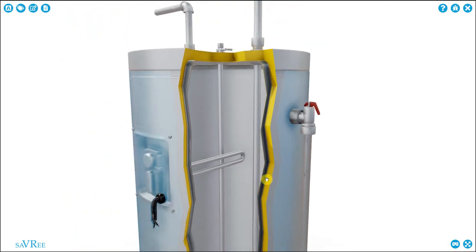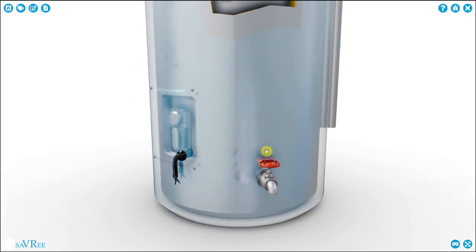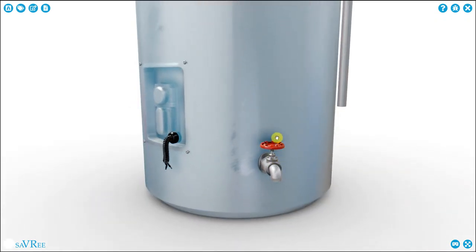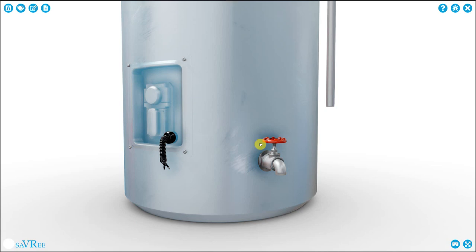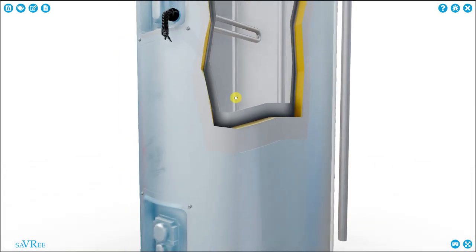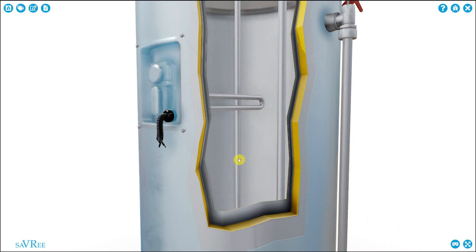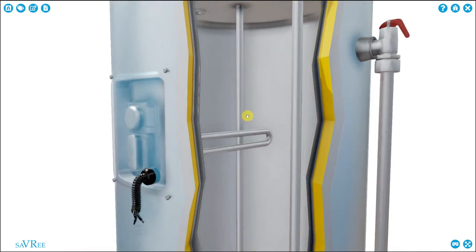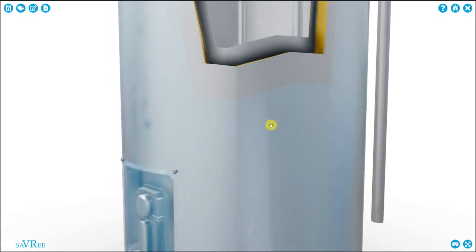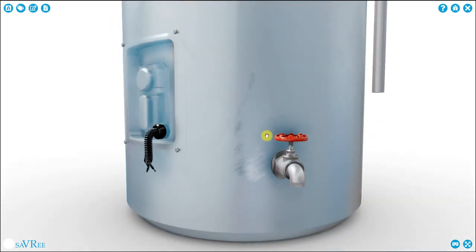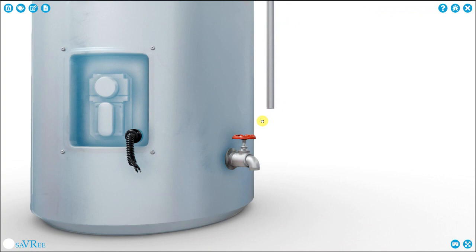Periodically, we can open up the drain valve to drain out any mineral deposits, any bits of scale, any bits of rust that might have accumulated in the bottom of the tank. And when we open up the drain, we might also get bits of the sacrificial anode being drained as well. When the anode is quite corroded, little bits of it break off. And these bits will gather at the base of the tank and we can drain them out using the drain valve.